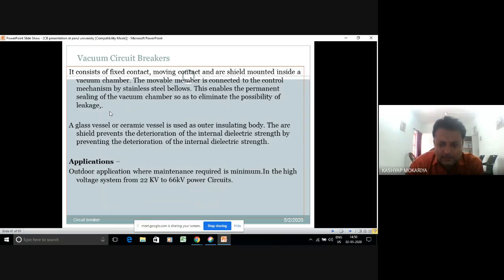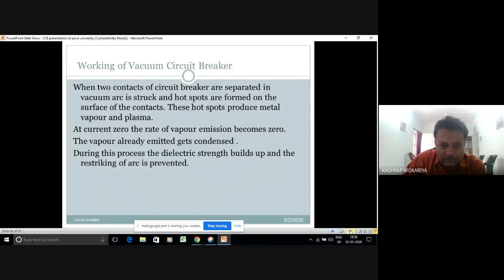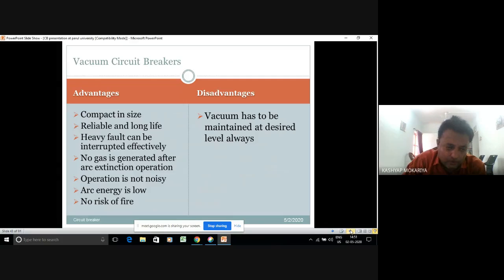For outdoor application where maintenance required is minimum, in industry I generally work with two ratings for VCB, that is 6.6 kV and 33 kV. When the two contacts of the circuit breaker are separated in vacuum, an arc is struck and hotspots are formed on the surface of the contacts. These hotspots produce metal vapor and plasma. At current zero, the rate of vapor emission becomes zero. The vapor already emitted gets condensed, and hence the dielectric strength is built, which can take care of your arc.